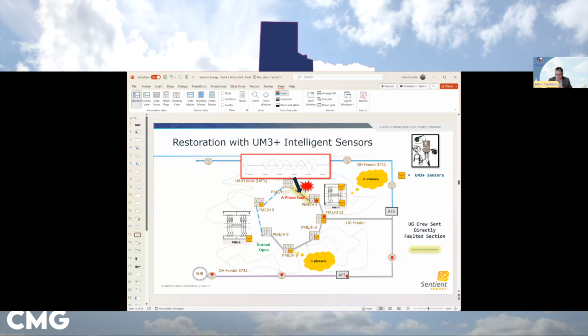With appropriate switching, you're able to isolate the fault—we like to say we make FLISR better. We can tell you where the fault is and where you can use your recloser scheme to come back in, not onto the fault itself, but to minimize the number of affected customers, which also improves safety.